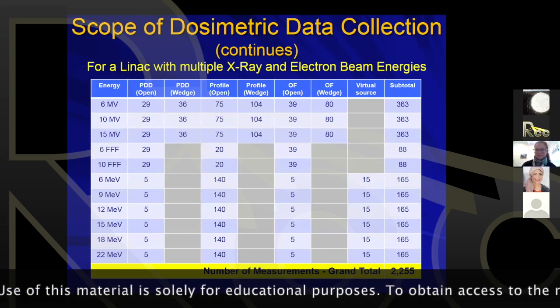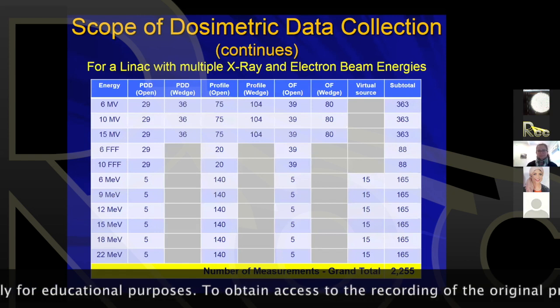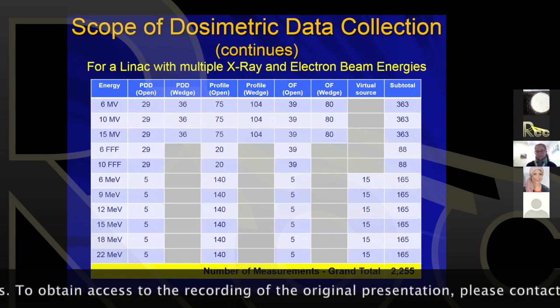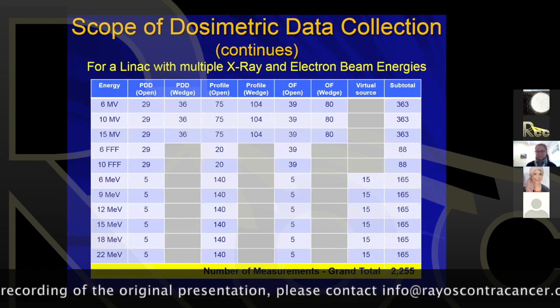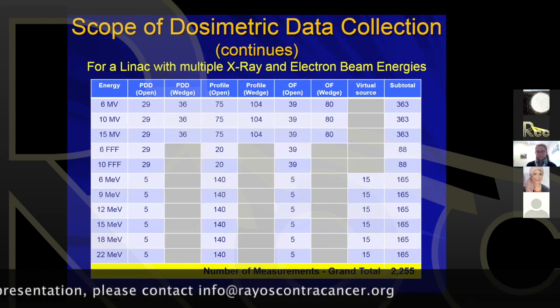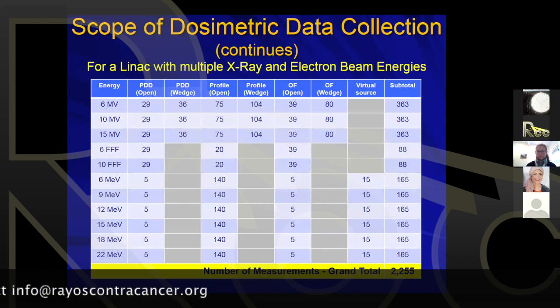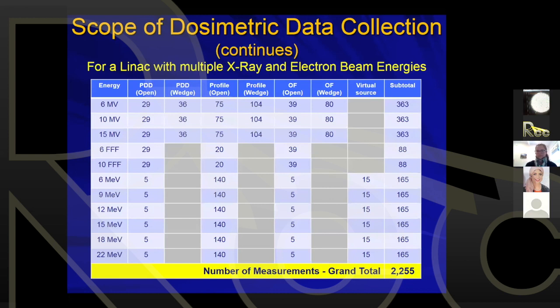Sorry, a brass buildup cap? No, we don't use a brass buildup cap during commissioning. Everything is done in water. So all you do is waterproof your chamber. That's basically it. No brass buildup. You need to set up your water tank, and then typically for the PDDs and profiles, you use a CC13 chamber, or you can use a specific diode for large fields, and collect your PDD and profile data that way.